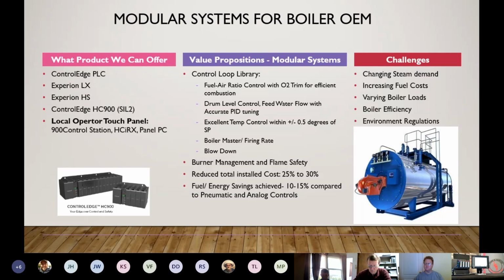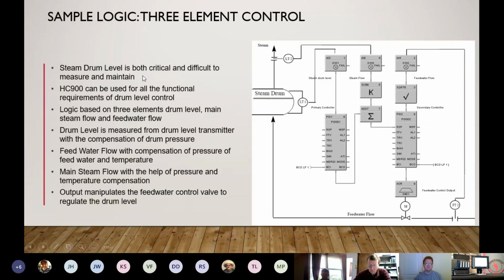If you have varying boiler loads, the HC900, along with the fuzzy logic and some feed forward or cascaded control, you can really minimize the upward and downward swings in the boiler loads. Boiler efficiency, environmental regulations, these are some of the other challenges you can address with the fuel air ratio and those type of features in the HC900. Last couple slides here, this is an example of a 3-element control. It shows the field with the steam drum level, the feed water and so on, along with the configured function block scheme that goes along with the 3-element drum control.